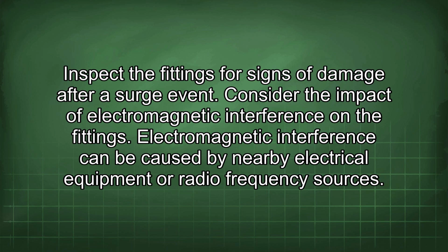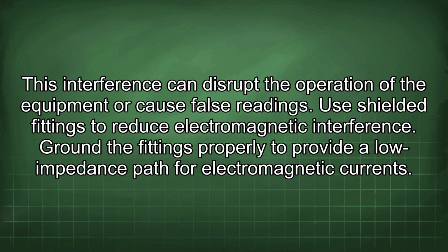Consider the impact of electromagnetic interference on the fittings. Electromagnetic interference can be caused by nearby electrical equipment or radio frequency sources. This interference can disrupt the operation of the equipment or cause false readings. Use shielded fittings to reduce electromagnetic interference. Ground the fittings properly to provide a low impedance path for electromagnetic currents.